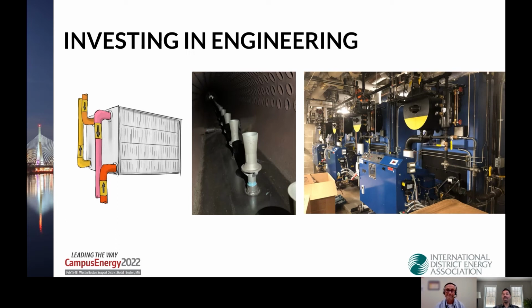Another example was the conversion of the existing steam boiler from steam to hot water. What you see on the screen are nozzles welded into the bottom drum of one of the steam boilers in the central heat plant. We came up with that solution instead of replacing those old but still usable boilers, which were built to last many years. This reduced implementation time, since we don't have to demo those big boilers, find space for new ones, or manage a very complex replacement schedule, because we're reusing most of the existing assets. The engineering just had to be done in a way that would work for the future, so we spent more time with specialists figuring out how to convert them to hot water, but it paid off in the end.